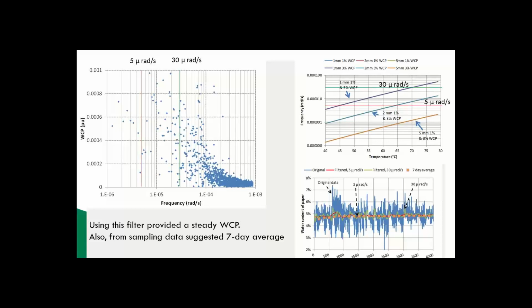And then we were also trialing other measurements. So then we were looking at the 5 micro. And this was looking at, suppose we have a lower temperature in our transformer, then we can use that in our frequency cutoff. So on the graph on the left as well, I hope you can see the red and the green lines. This is the general effect on our frequencies. We are saying we're going to keep everything to the left of either the red or the green line. Anything to the right is either noise or the temperature changing too quickly. So if we keep everything to the left, then we should keep these very slow changes in moisture content, and then we can start to remove the daily fluctuations being seen by the sensor.